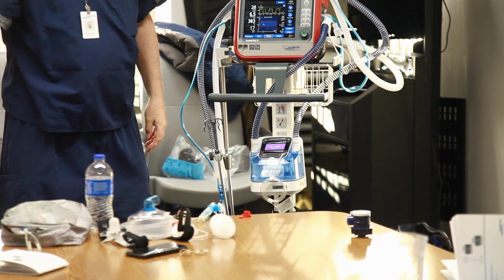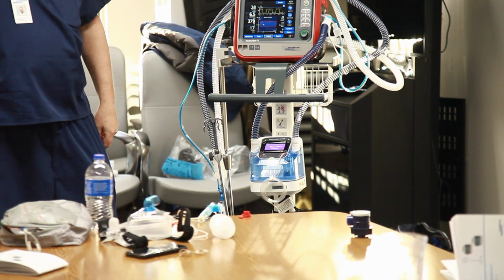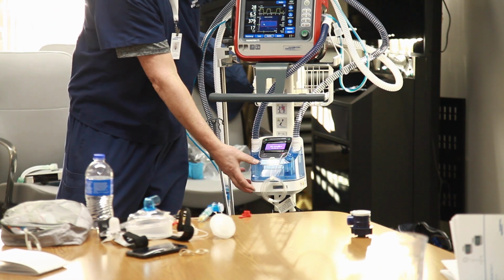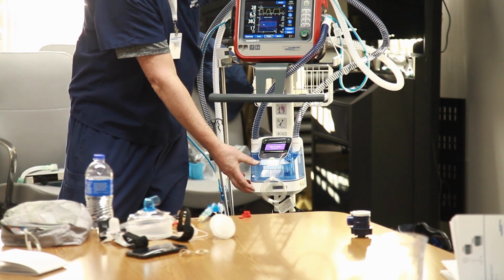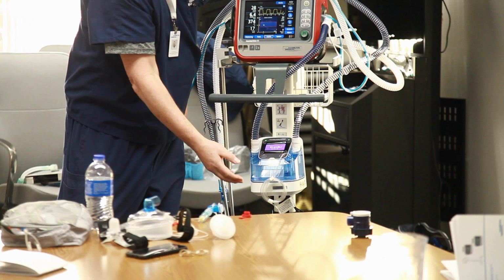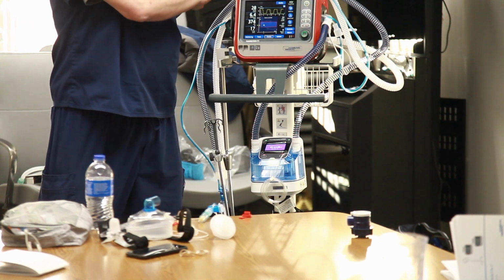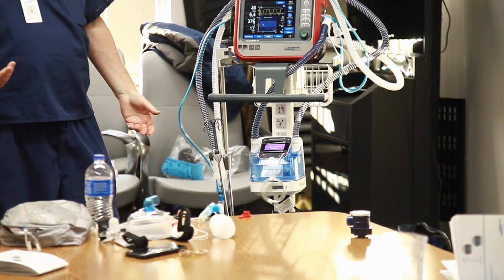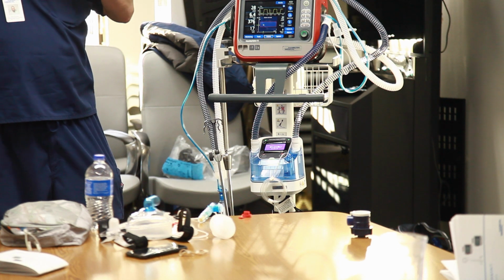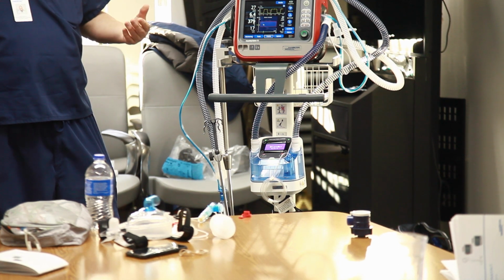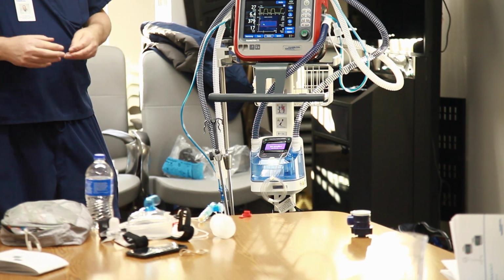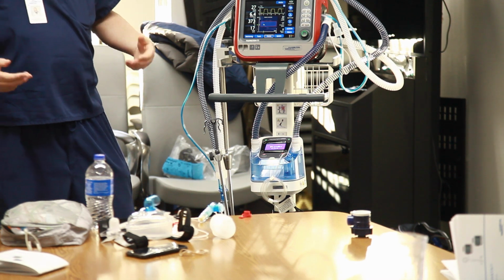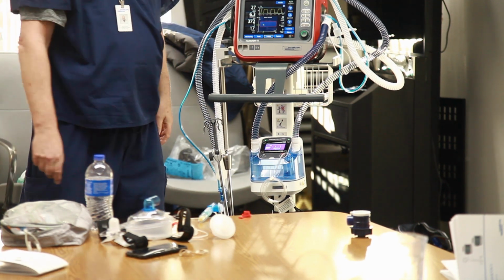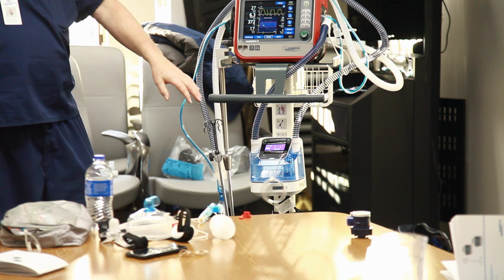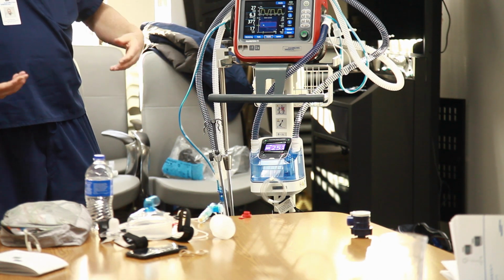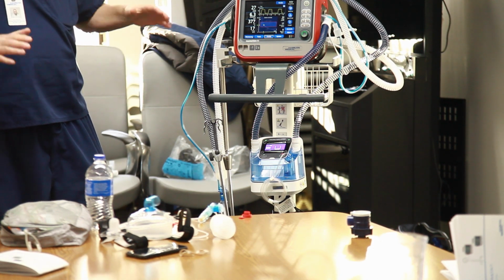Push this button once, it goes to standby. Now this humidifier is going to go down to 28 degrees. They're not quite as warm in your tubings. So if it's too much, too steamy, too wet for your patient, just hit standby. If they're complaining later that it's too dry, just push this and start it again. I can only get like 1 degree cooler than that, and I have to do a weird thing to get there. So it's just too much.